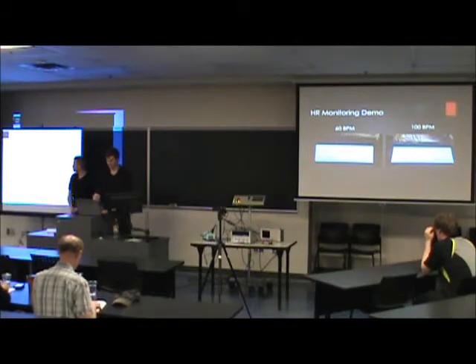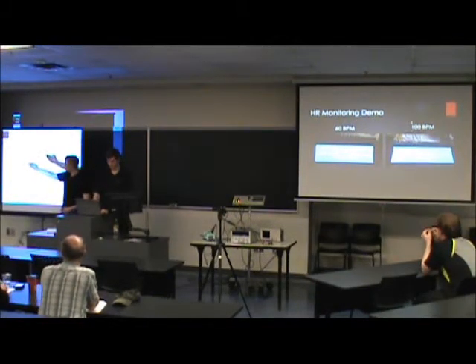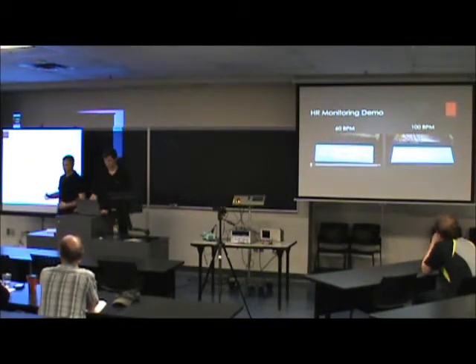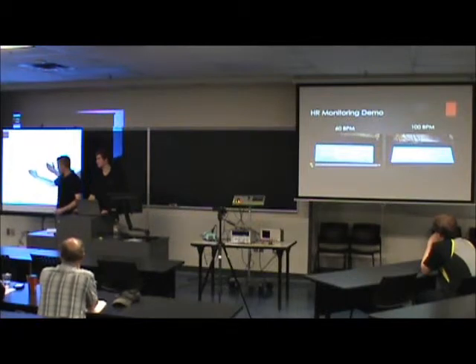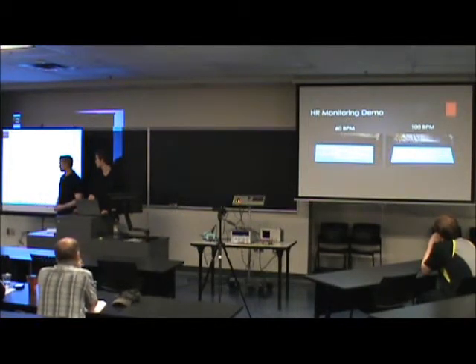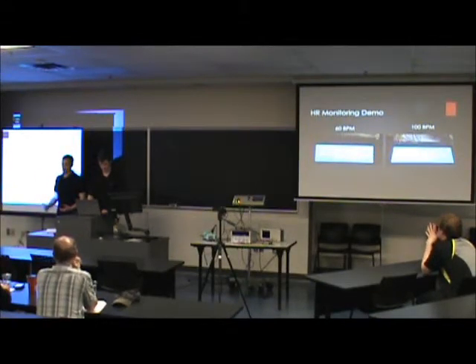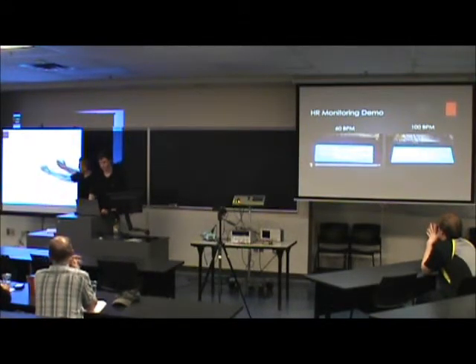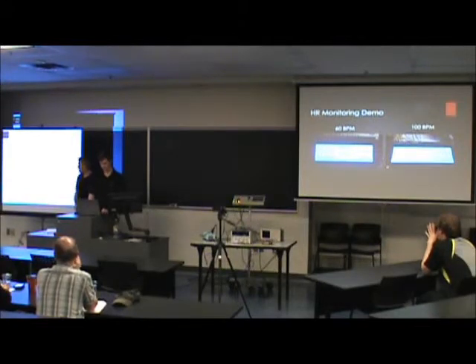So this is the message that we get on our heart rate monitor when we're testing. I've made it enabled, so you actually have to enable it to start your heart rate testing, because how this works is we use a 15-second time window to take the reading. We count how many pulses are in that 15-second time window and multiply that by 4, which gives us our output of beats per minute. So this is a video just showing our example of 60 beats per minute.